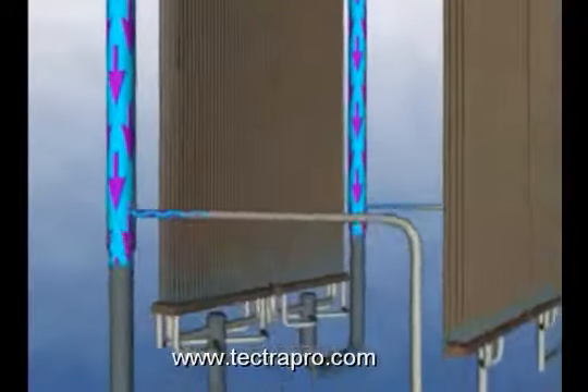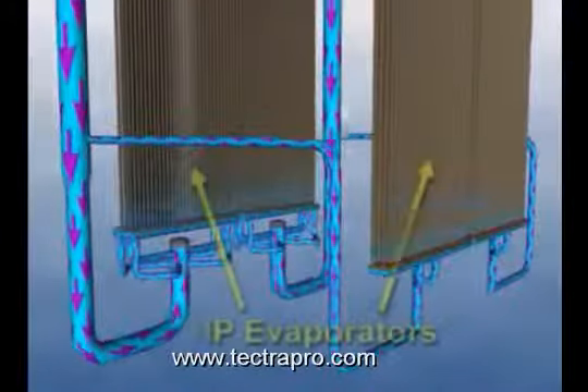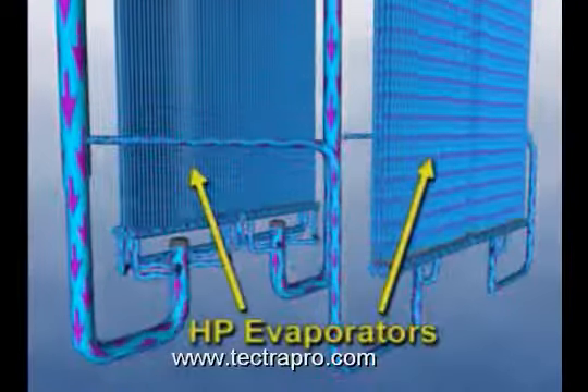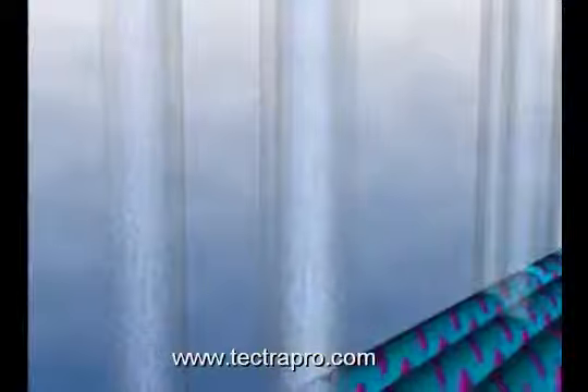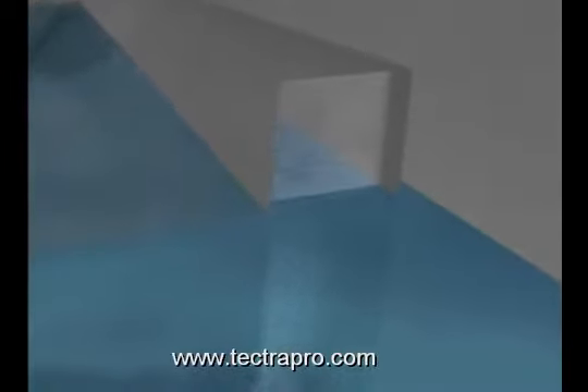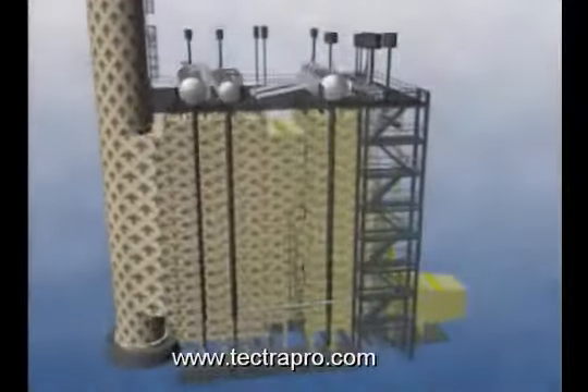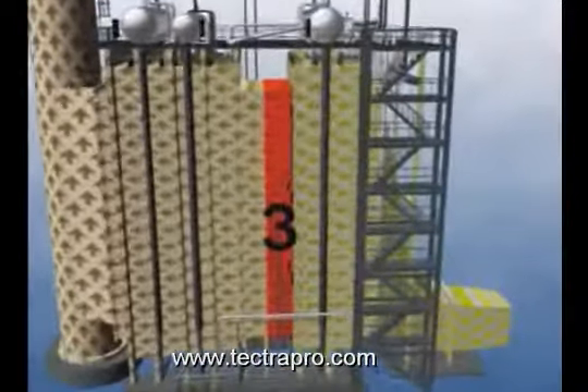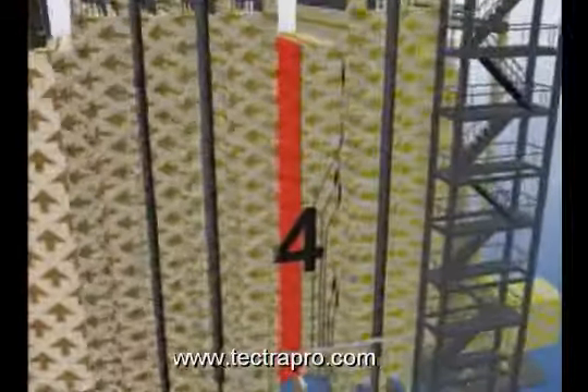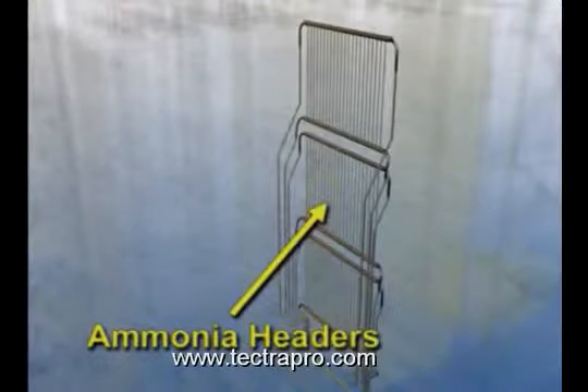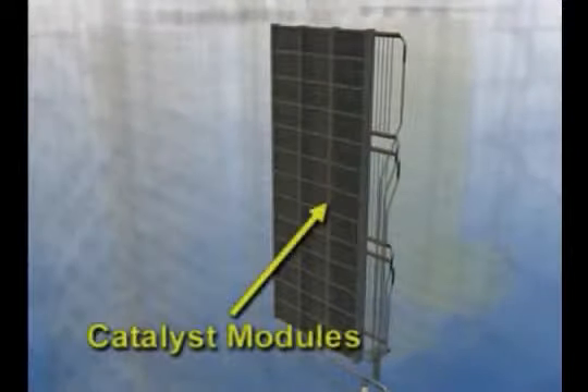Water from the HP drum flows through 5 HP evaporator racks and the steam-water mixture rises back to the HP drum. Boxes 3 and 4 separate the first and second HP evaporator racks and contain the SCR ammonia header and catalyst modules.